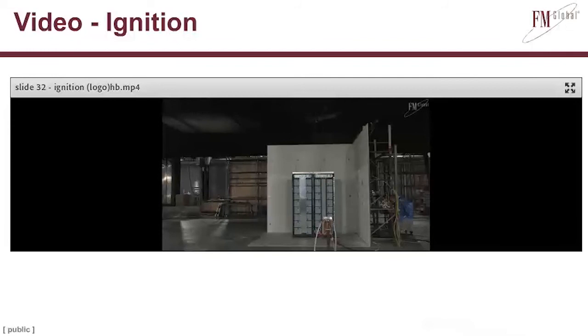So you can see here the ignition module is burning now. And again, that's for the NMC, that's done strictly with heat. This type of battery has a tendency to spark as it goes into thermal runaway, so as the flammable gas comes out of the battery, the sparks will cause ignition. That's the only module that has any form of imposed heating. Any additional fire spread from there is based on the fire occurring in that initial module, and so this can be a bit of a slow process.